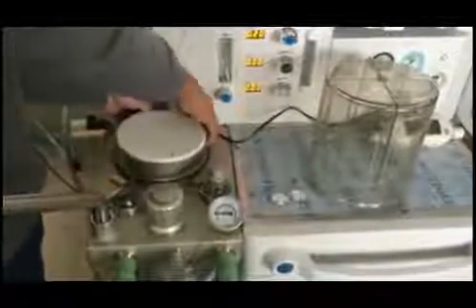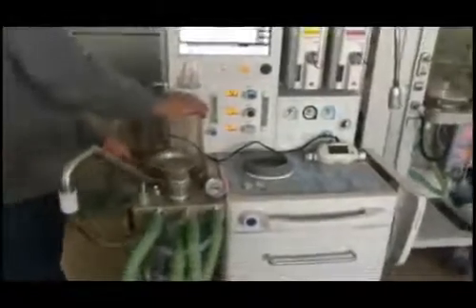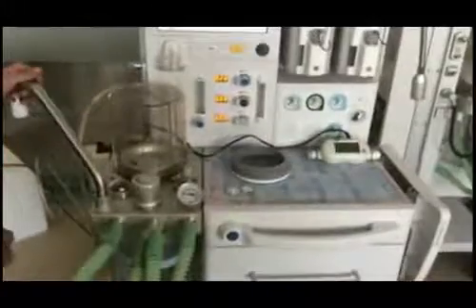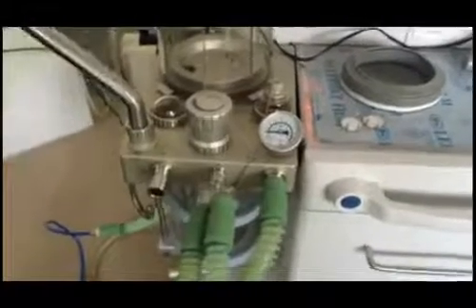In order to remove the bellows, first remove the bellows cover. This is the bellows cover. This is the bellows. After removing the bellows cover, place back the bellows cover. The next step is to seal the expiration port. This is the expiration port. Now we seal the expiration port using this.